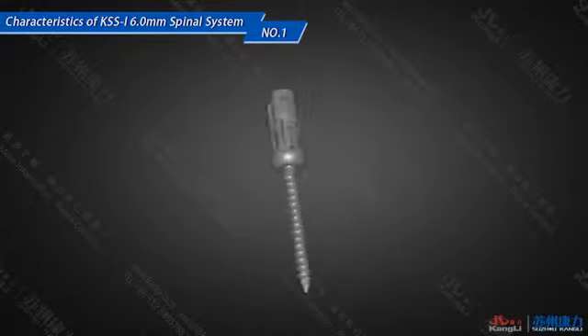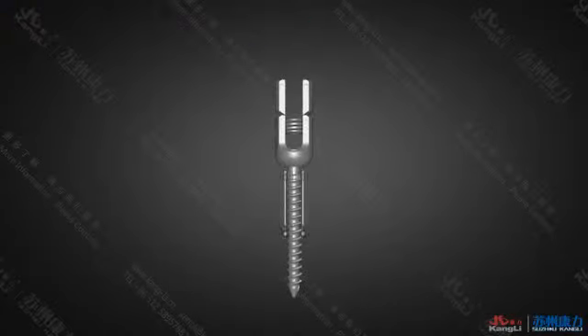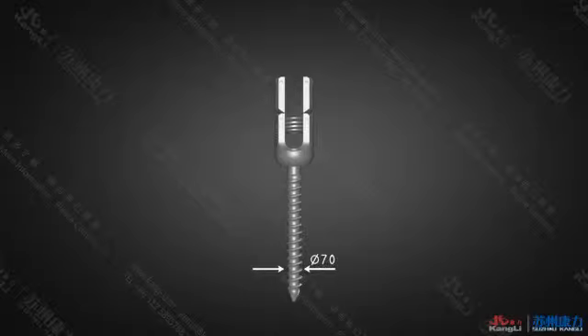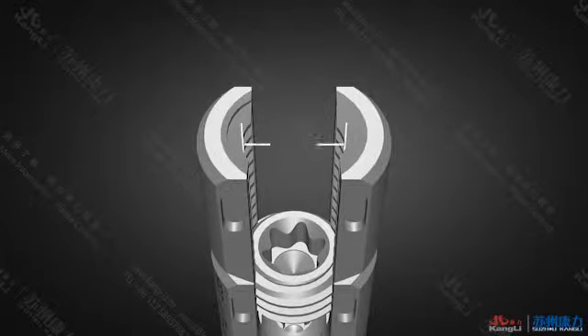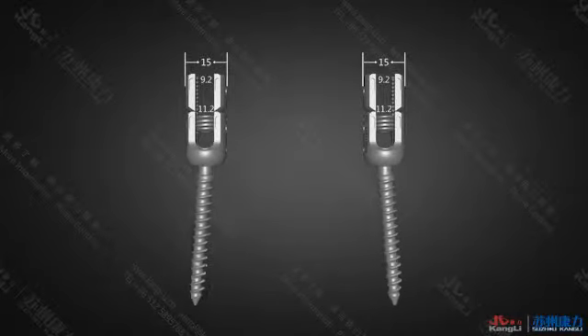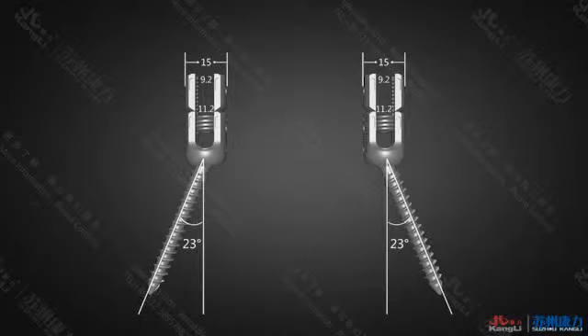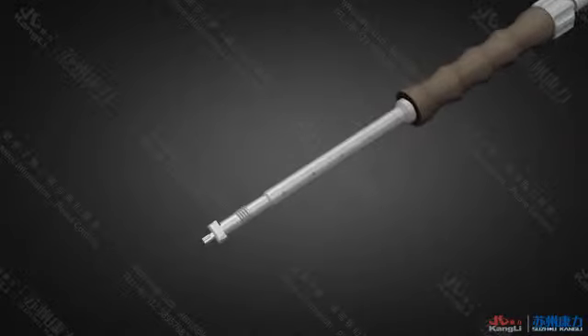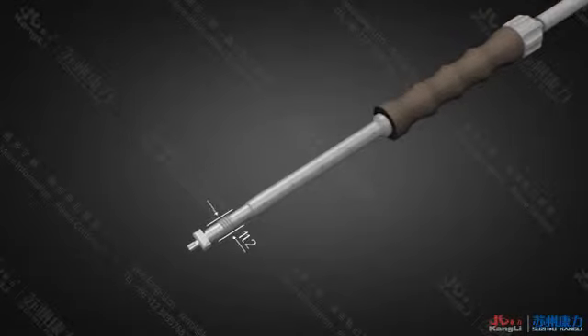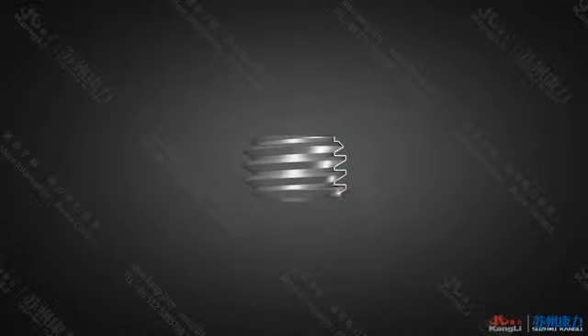Due to the special design, the head of the 7.0 millimeter and 7.5 millimeter multiaxial screw can rotate 23 degrees in any direction, thereby meeting various demands in different clinical practices. The screw can be easily planted with the unique instrument. The triple-thread design of the plug screw effectively prevents the rod from loosening, and the torque design on the top also greatly reduces the risk of sliding.